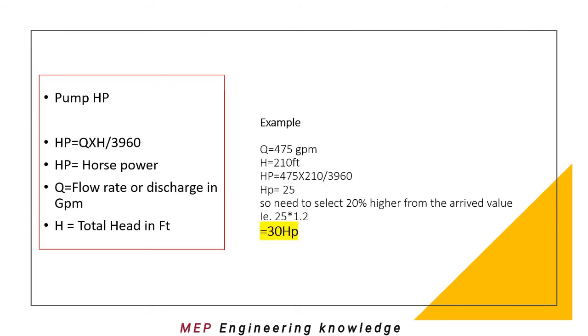Let us see an example: from this video we have 1800 LPM, which converts to approximately 475 GPM. After arriving at the building height, vertical pipeline, fittings, and converting into length, we arrive at 210 feet. Using the formula: HP = 475 × 210 / 3960 = 25 HP. We need to select 20% higher than the arrived value, so 25 × 1.2 = 30 HP. Depending on pump efficiency, we select accordingly.